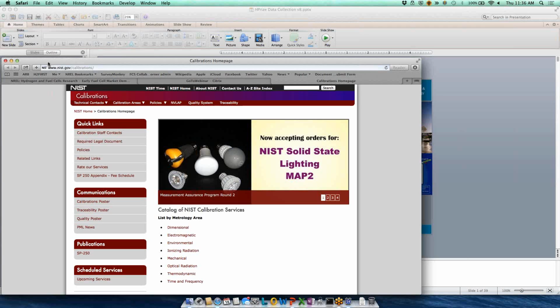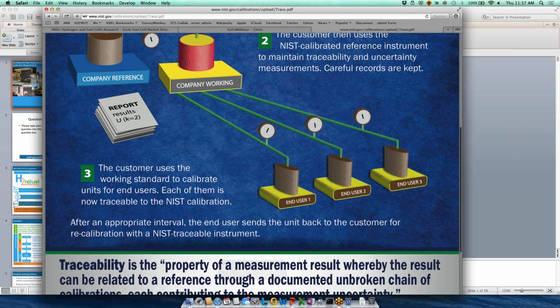NIST will keep the standard. The company's reference standard will then be used to keep calibrated a company working standard that will be on the manufacturing line, and that will be used to calibrate the individual devices that will be installed. That's what we mean by traceability.